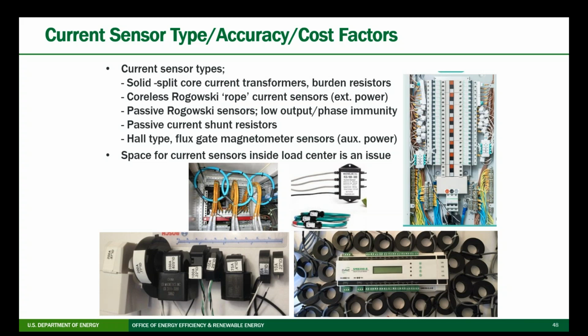Going down, we have these solid and split core current sensors, Rogowski type flexible rope sensors, and passive Rogowski sensors, which are in the middle of that stack. They're low cost but have phase immunity. They have some noise issues—if you put them too close to other signals, they lose accuracy.